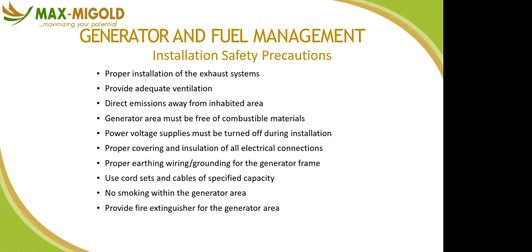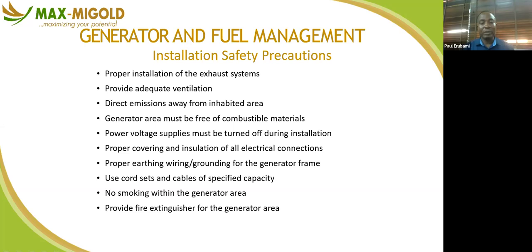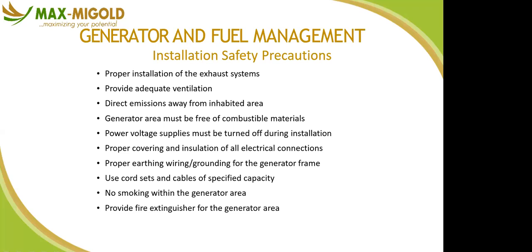So you must not put cartons and paper around your generator, because if there's any problem like fire, those cartons and paper will act as additional fuel. They will make the generator burn fast and easily, where you will need maybe a 5 kg fire extinguisher to put off a fire incident around your generator. It's unstable, okay? So you'll now be looking for 25 kg, as the case may be. So it's better you clear your place of combustible material.